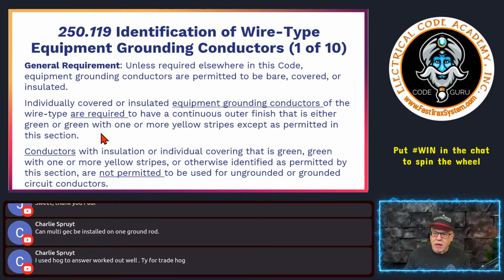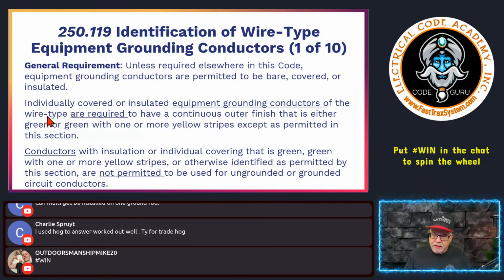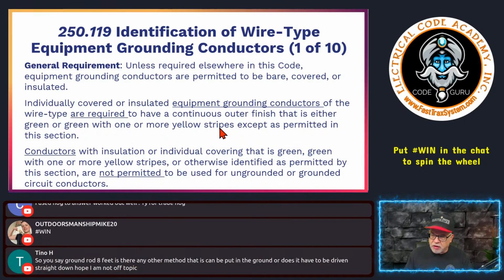Okay? Now, individually covered or insulated equipment grounding conductors of the wire type are required to have a continuous outer finish that is either green or green with one or more yellow stripes, except as permitted in this section. So again, we're permitted to be bare, but when we do insulate it, if I have an individually covered or individually insulated equipment ground, then it's going to be green, or green with yellow stripes.